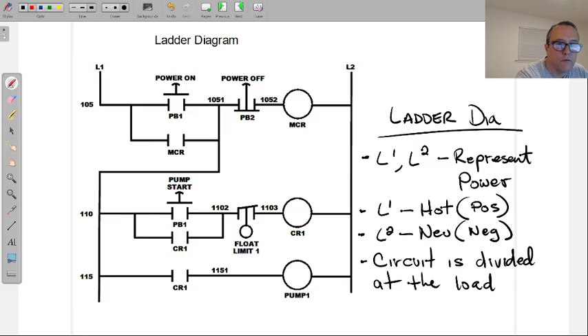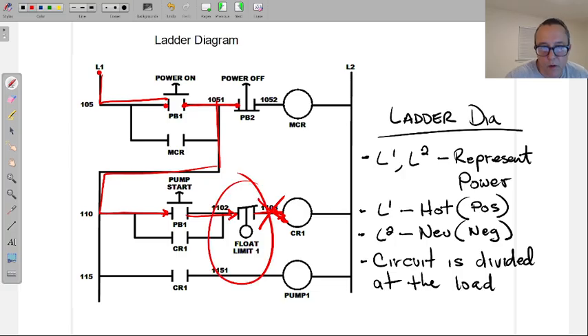You check power from that point to that point. Do I have power? Yes, no. I have power? Good, this one is fine. Point to point. Do I have power between this point? Yes, no, I have power, good. And we continue down the line. Do I have power here? Yes, no, and so on. Power here? Yes. Power here? No power here. Okay, something's going on with this float switch. It's that simple, it really isn't any harder than that.